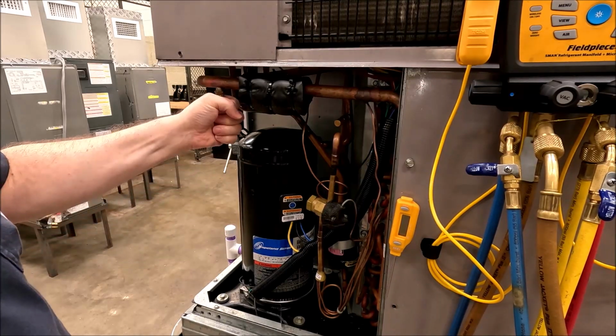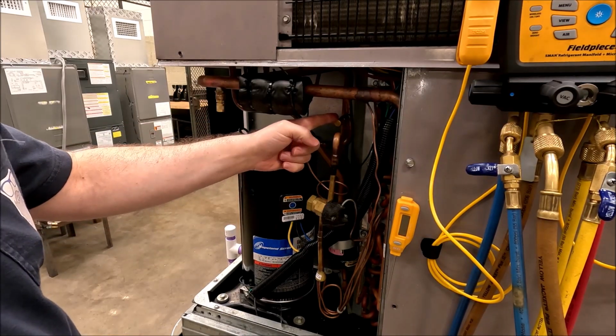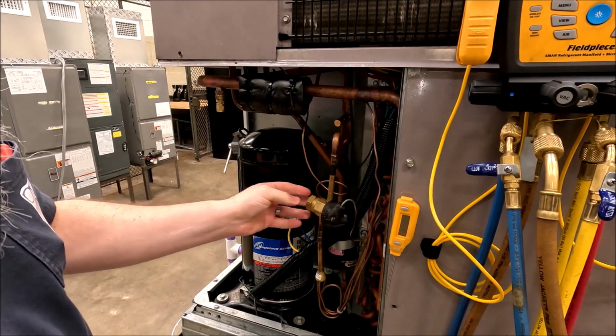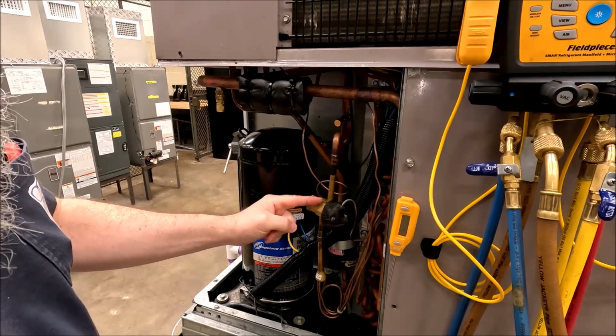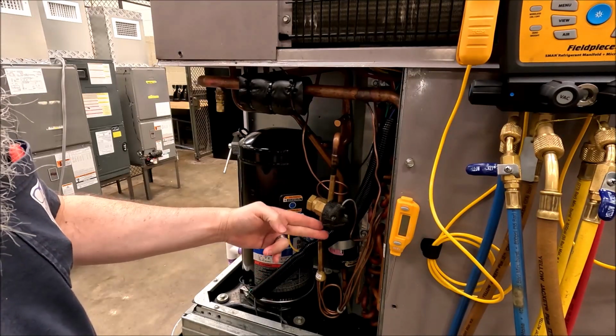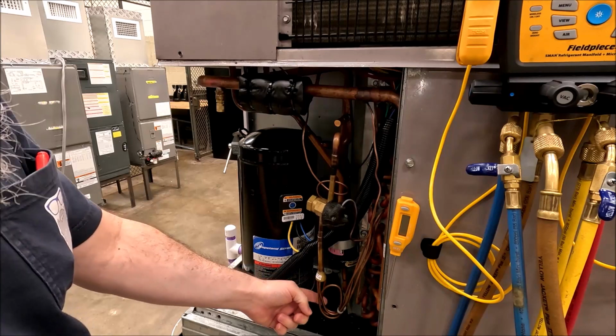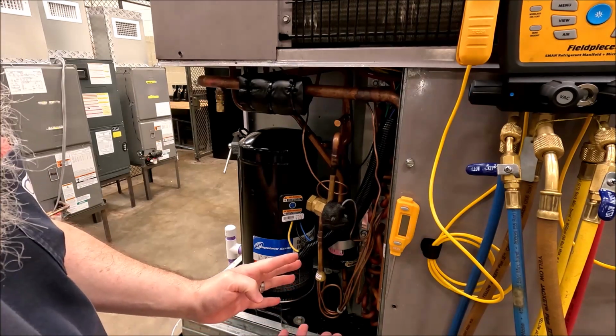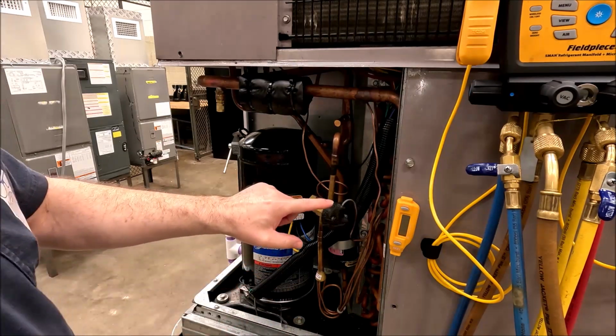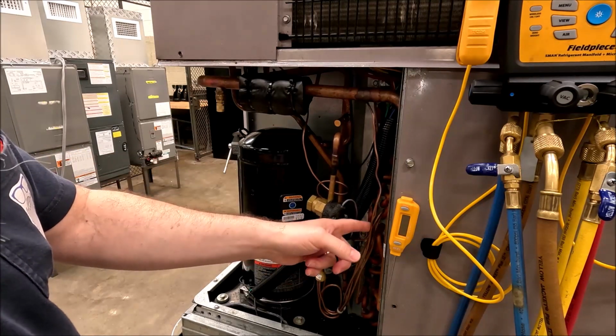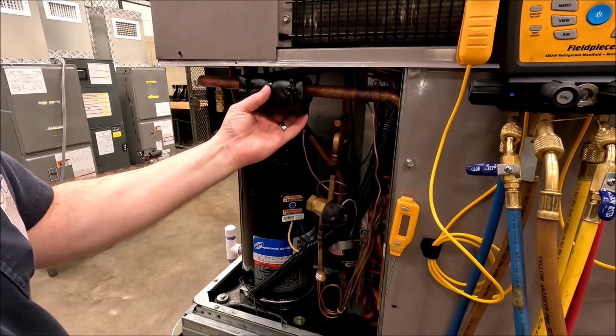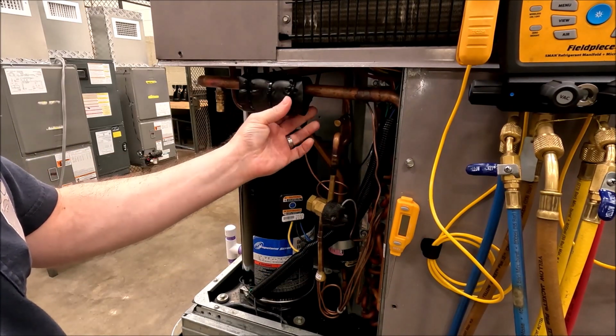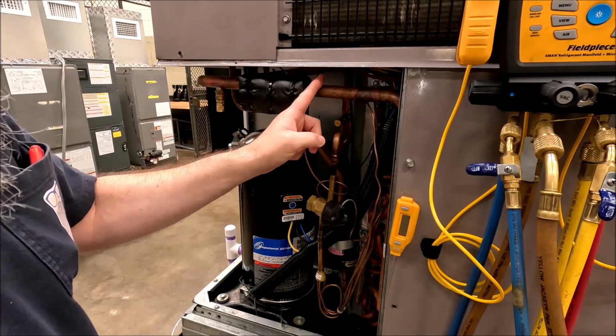I see a brass cap, another brass cap here. I see this big brass body. That's my metering device. So this is going to be my distribution area. You can see how it splits into 3 tubes on this one. The last one was 4. I can notice that my TXV capillary goes up here to the bulb. So that better be my vapor line.